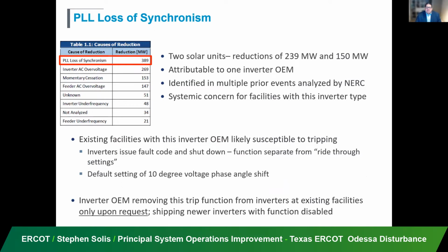When we look at the PLL loss of sync, these were two solar units primarily. And in terms of which inverter OEMs were involved, it was really one OEM in particular that had these issues. What was interesting is that this inverter OEM has fixed this issue moving forward with new installations. But for the existing installations, while they have a fix, they're only implementing it upon request. So awareness of this issue is important so that existing facilities can correct the issues, and new facilities ensure they have the proper settings from the beginning.